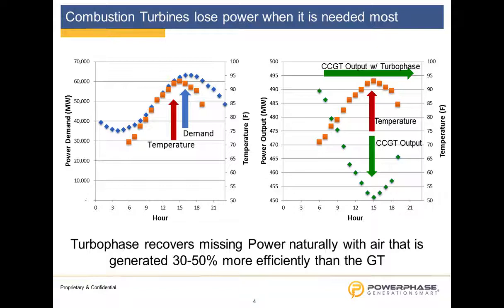So Turbophase works when your power is needed the most. Demand across the world also grows with increasing temperature, as both industry users and household users require more electricity. So when the gas turbine performs its worst is when you actually need the most power. If I overlay this with wind, in most of the world the wind stops blowing as it gets hot, so it is also the point at which you have the worst wind production, and then you can balance solar into that as well, as an intermittent resource. Turbophase is there to make the gas turbine respond to changing ambient conditions so that we can have a baseload, consistent output instead of a variable output with the weather.